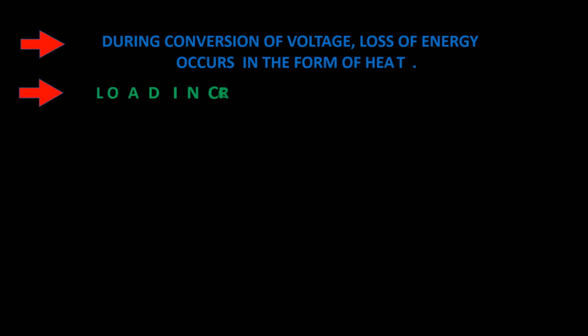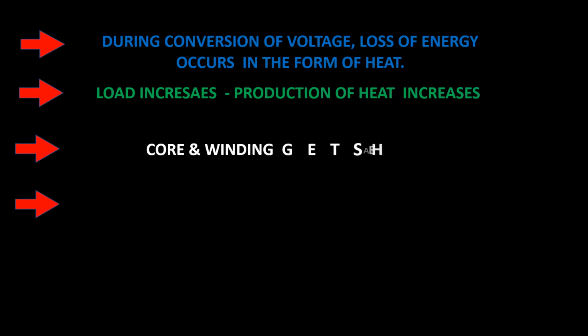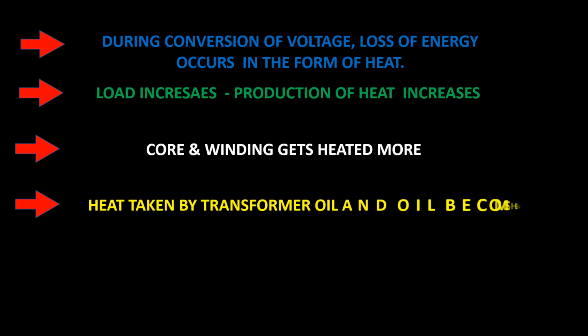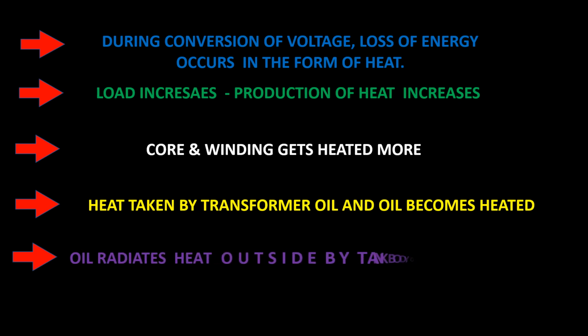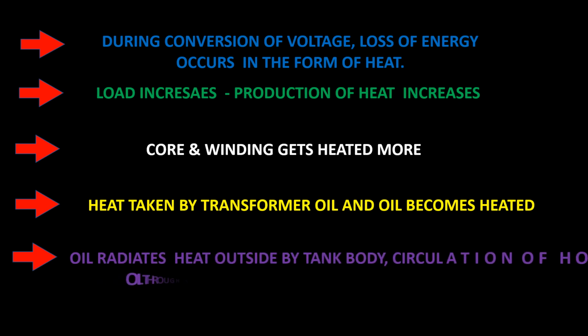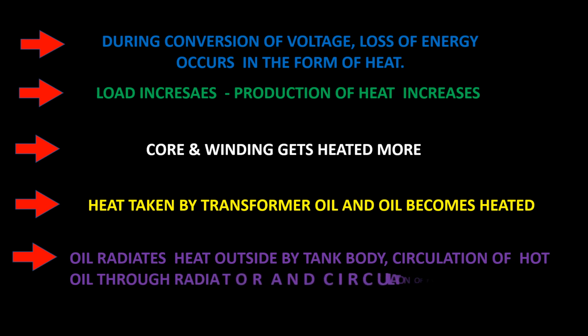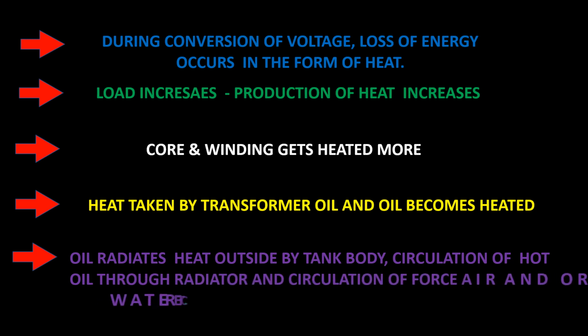We know a transformer needs cooling when load increases, due to loss of energy in the form of heat during conversion of voltage and thereby feeding of load. Core and winding become heated. This heat is taken by the transformer insulating oil. Thus, the temperature of the oil is increased. So, the transformer oil needs to reduce its excessive temperature by the support of cooling apparatus, for maintaining a suitable temperature to prevent any damage to the insulation as a whole.